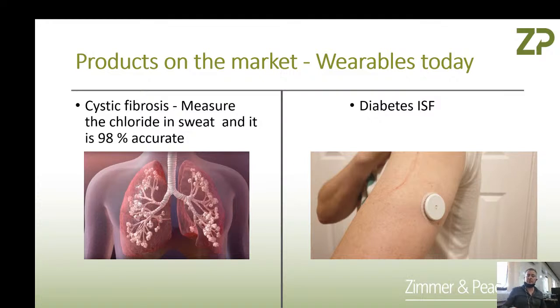How does ZP overcome the challenges? In order to make a CGM sensor at a high standard, most companies on the market have spent at least $50 million doing it. It's all solvable, but there's no secret sauce — it's effort, and effort equals investment. We do it through good sensor design, good electronics, good data science, and large teams on these programs. We spend about 10,000 hours per year doing continuous glucose monitoring type projects over several years. It's how to make sensors good — it's effort, and effort by the right types of people.